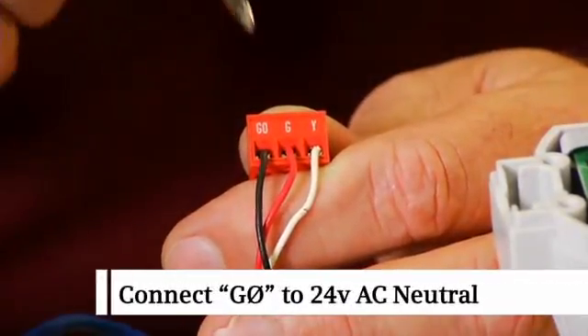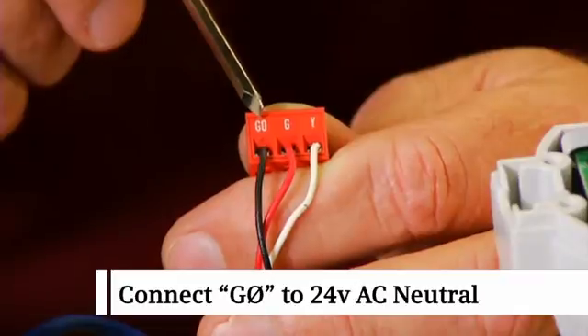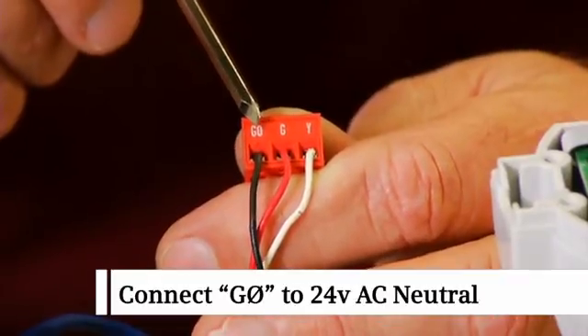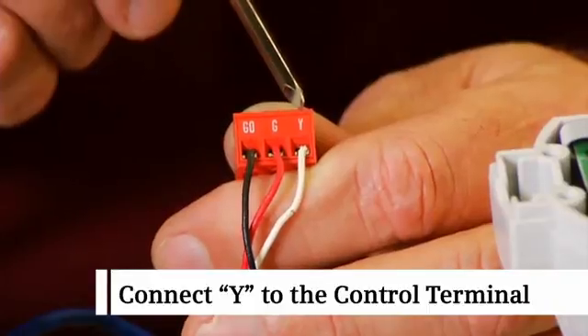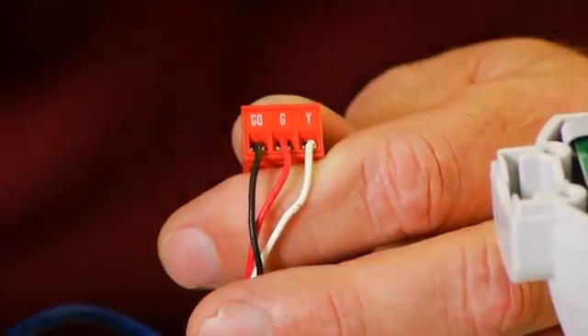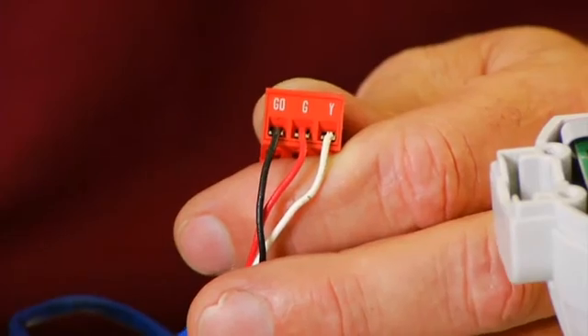Connect G0 to the 24 volt AC neutral terminal, and connect Y to the 0 to 10 VDC control terminal. Plug the terminal connector into the pins in the SSC actuator.